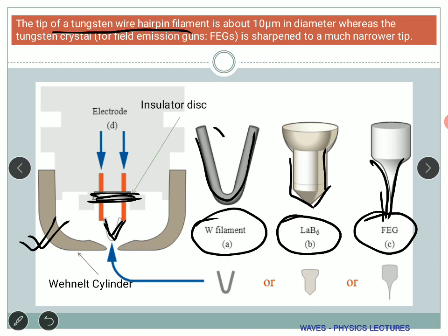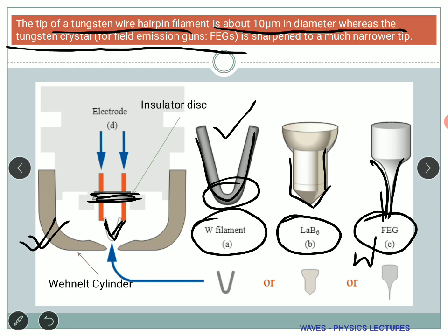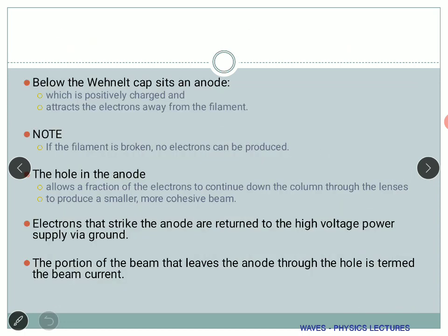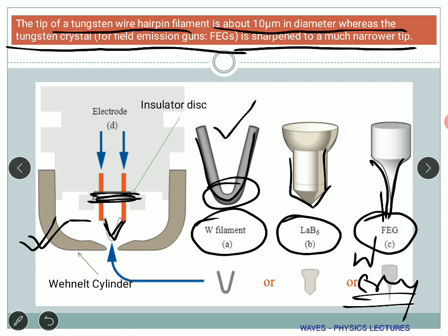The tip of a tungsten wire is about 10 micrometers in diameter — it's just enlarged in the diagram. The tungsten crystal used in the field emission gun is sharpened to a much narrower tip in the nanometer range. The Wehnelt cap sits with an anode — the anode is positively charged and attracts electrons away from the filament. Any stray electrons flowing toward the positively charged anode are captured there.